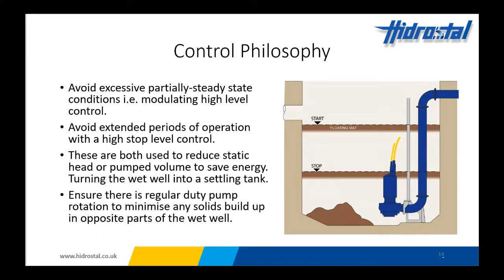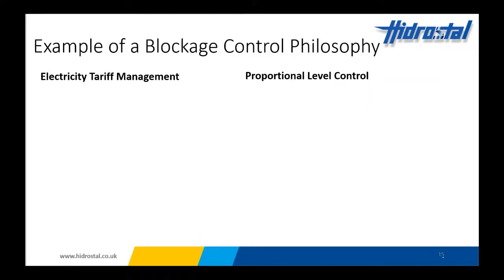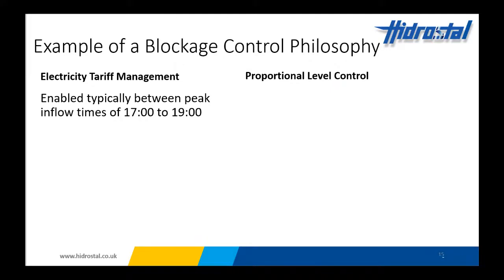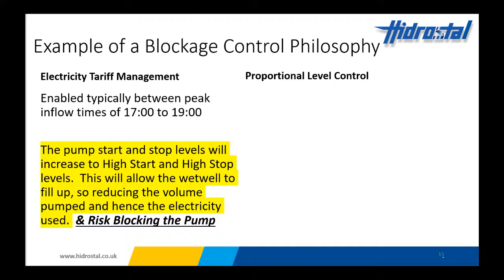Ensure there is a regular duty rotation as well. So that just minimizes any buildup of debris in one side of the sump compared to the other. An example of blockage control philosophy, as I'll call it, would be electrical tariff management. So during peak hours, 5 o'clock to say 7 o'clock, some people will think, well, I'm going to raise the level, pump less, reduce the static, but that comes at a price. You're probably going to block the pumps more.